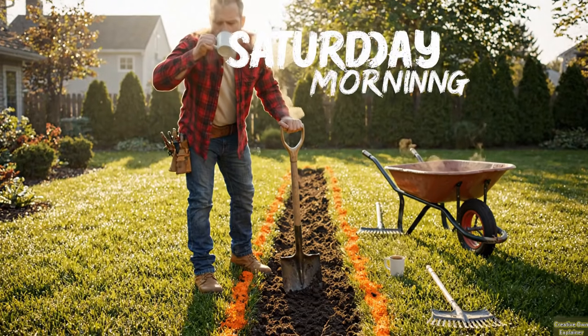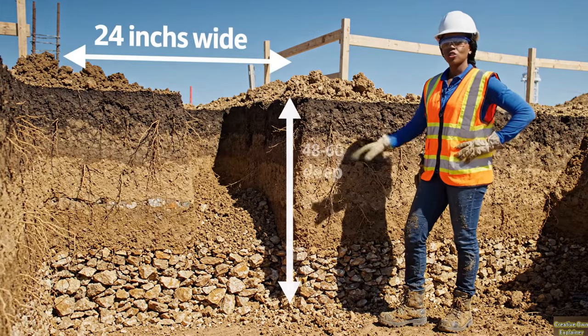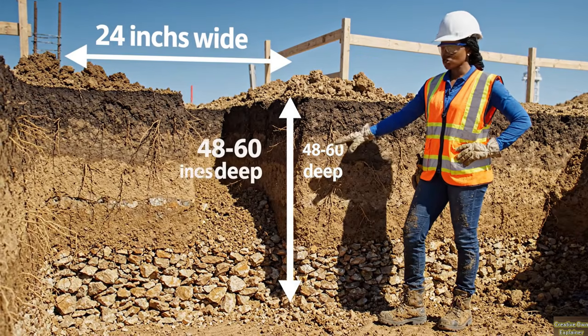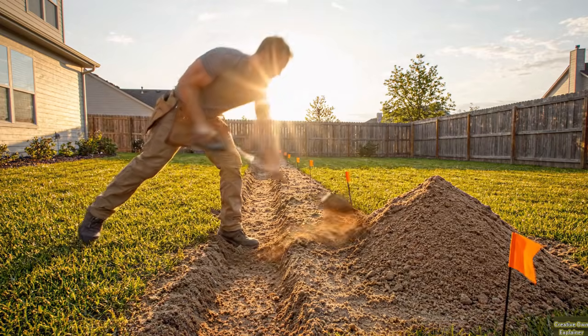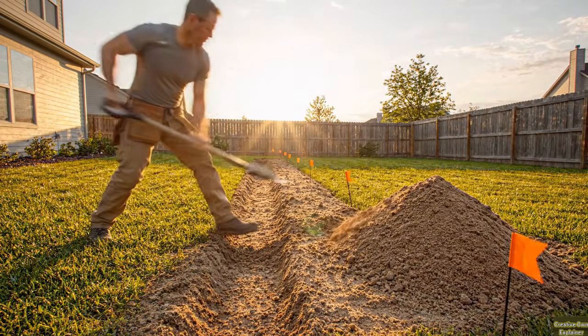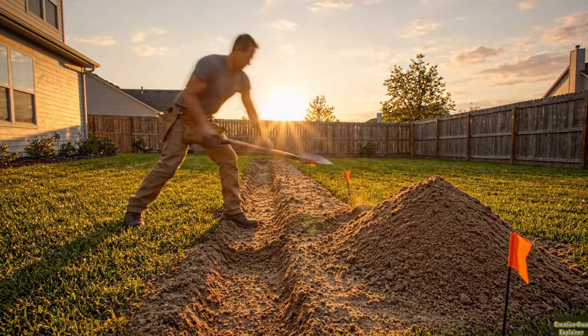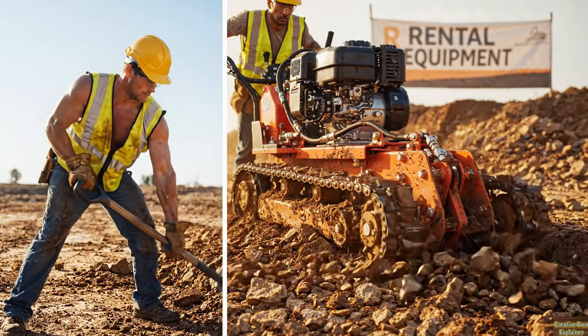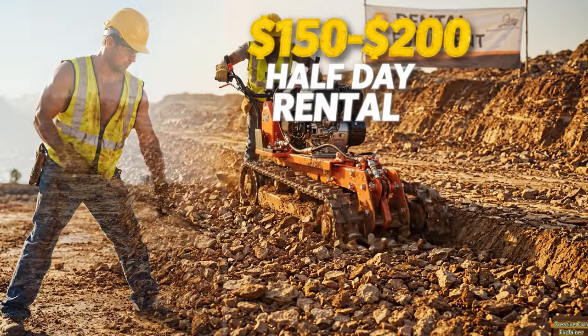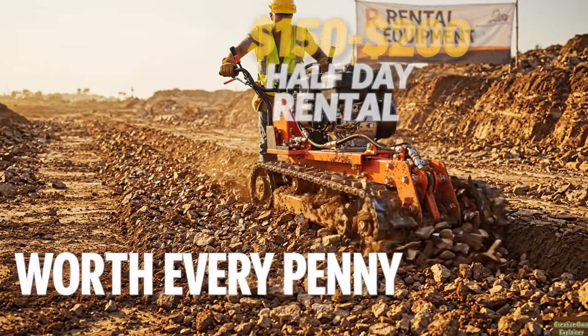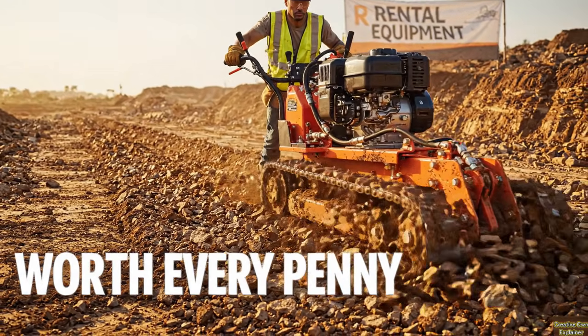Saturday morning, dig the trench. You need it 24 inches wide and at least 48 inches deep, ideally 60 inches. In loose soil, one person with a trenching shovel can dig 40 feet in 4 to 5 hours. In clay or rocky ground, rent a walk-behind trencher from any equipment rental shop for $150 to $200 for a half day. It is worth every penny.